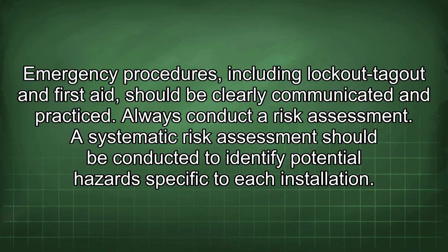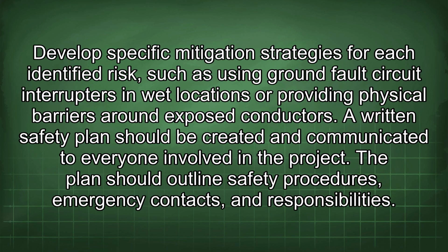Always conduct a risk assessment. A systematic risk assessment should be conducted to identify potential hazards specific to each installation. Develop specific mitigation strategies for each identified risk, such as using ground fault circuit interrupters in wet locations or providing physical barriers around exposed conductors. A written safety plan should be created and communicated to everyone involved in the project. The plan should outline safety procedures, emergency contacts, and responsibilities.